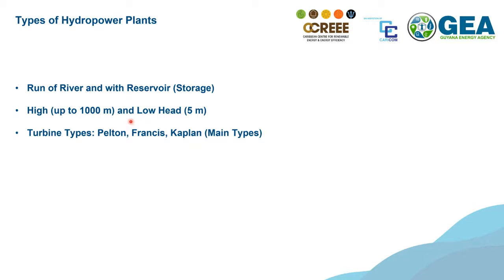Then it's very important to separate by the head. There are high head plants using potential energy - hydropower plants up to 1,000 meters in a single drop, a single penstock, so this is very high pressure, up to 100 bars. Or you can go to very low head inside a river stream, for example 5 meters or even less. So the range is very, very wide, and the types of turbines you need are also very different, and the size of the power plant too - it's directly connected to the head.